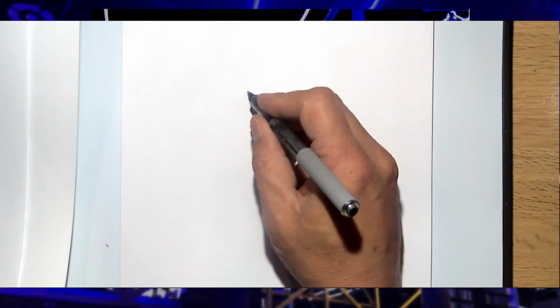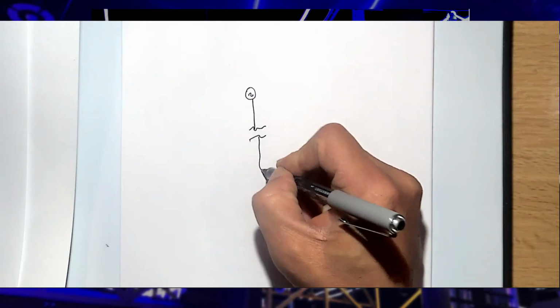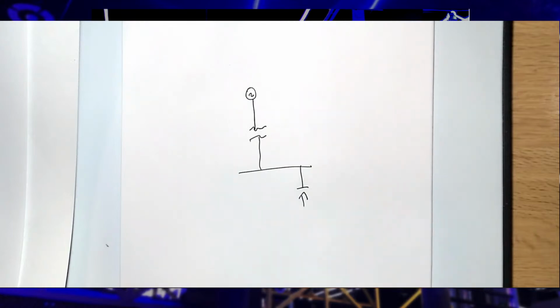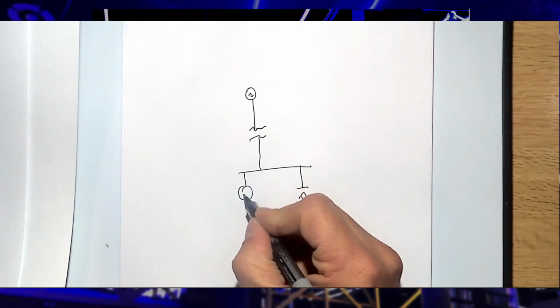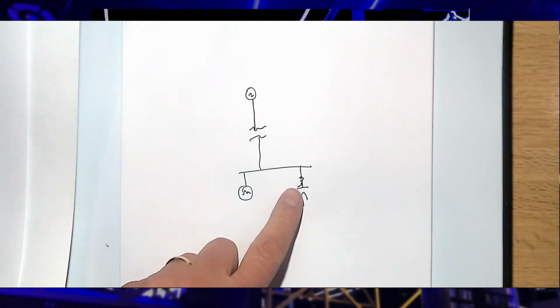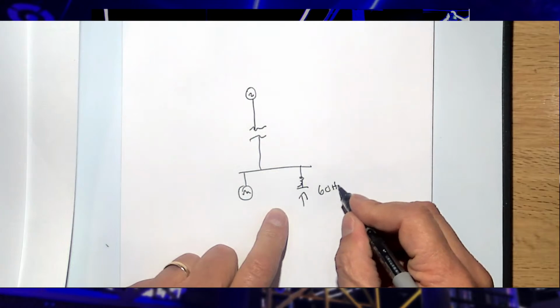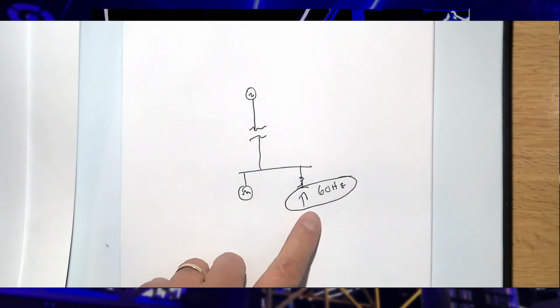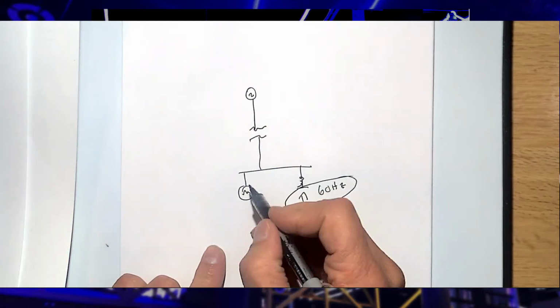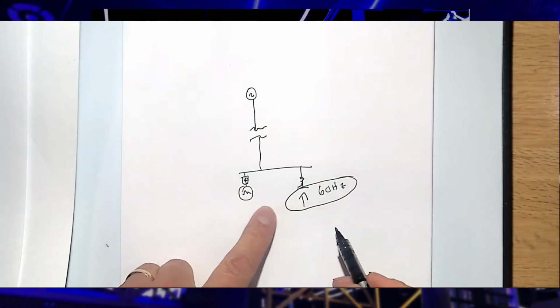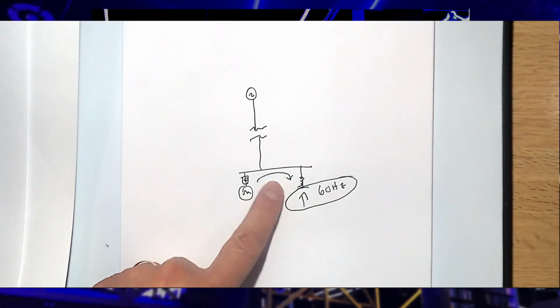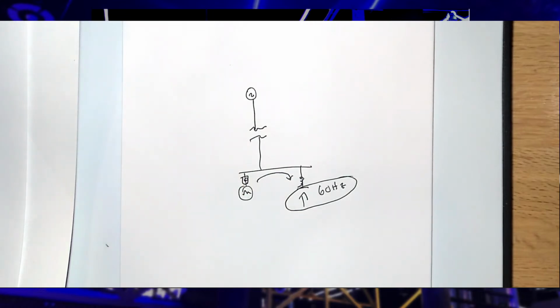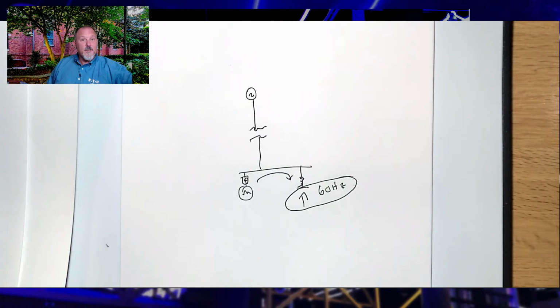So when I put on, for example, I'll show you. Again, I have my source and my transformer, and if I put a capacitor there, that's a 60 hertz compensation for all my other loads. If I put an inductor in front of that, the tuning point of that may be fifth harmonic, or whatever frequency I'm trying to roll out, but at 60 hertz, it mostly looks like a capacitor. So if you knew you had variable frequency drives and other stuff here, you would make this into a harmonic filter so that you don't interact from a harmonic standpoint. That's a whole other discussion. We talk about resonance and everything there, but that sounds like a good idea for another program.